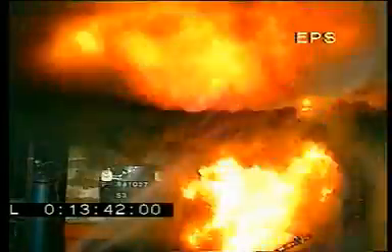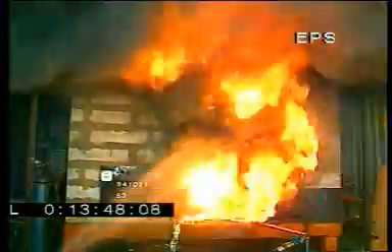In some small-scale tests, fire-retarded polystyrene has been certified as difficult to ignite. In this more realistic large-scale test, however, difficult to extinguish seems more appropriate.